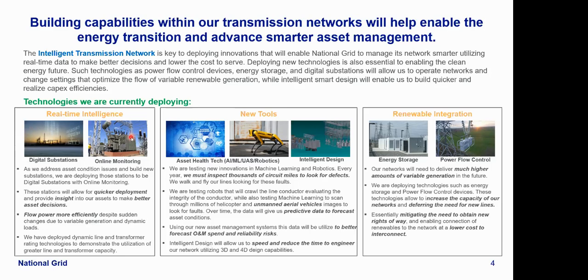The other technology that I'm going to highlight here is called online monitoring. In order to deliver clean energy to the customers, the first and basic thing you need is the grid. With that grid, if you want it condition-based, one of the basic things you need to keep in mind is: how can I save my transformer from catastrophic failure? How can I save my lines from failures, and so on? The best answer, or the only answer to that, is to have online monitoring technologies which give you real-time information on the health of the asset.